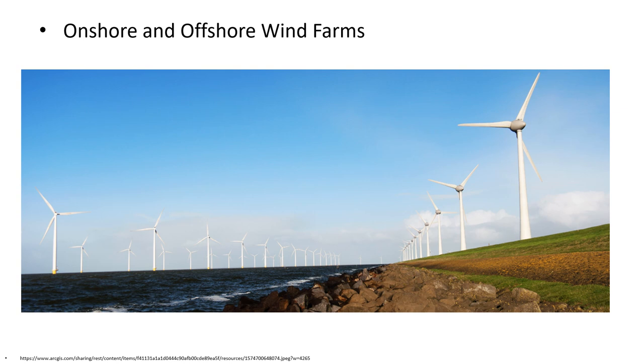Almost all large wind turbines have the same design: a horizontal axis wind turbine having an upwind rotor with three blades attached to a nacelle on top of a tall tubular tower. In a wind farm, individual wind turbines are interconnected with a medium voltage, often 34.5 kV, power collection system and communication network. A distance of 7D — that is, 7 times the rotor diameter — is set between each turbine in a fully developed wind farm. At a substation, this medium voltage current is increased using a transformer for connection to the higher voltage electric power transmission system.